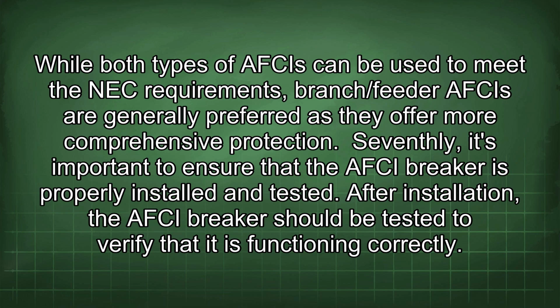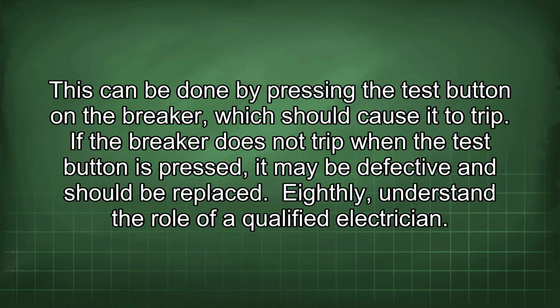Seventhly, it's important to ensure that the AFCI breaker is properly installed and tested. After installation, the AFCI breaker should be tested to verify that it is functioning correctly. This can be done by pressing the test button on the breaker, which should cause it to trip. If the breaker does not trip when the test button is pressed, it may be defective and should be replaced.